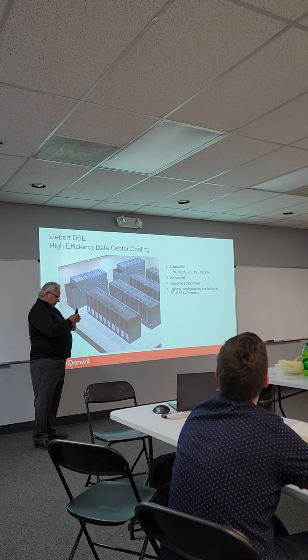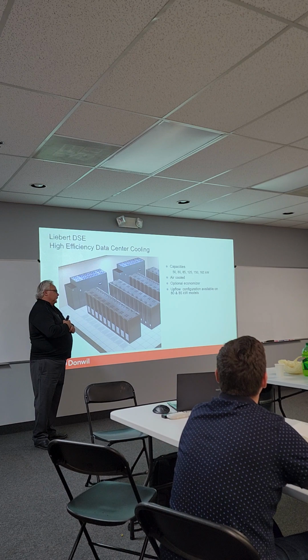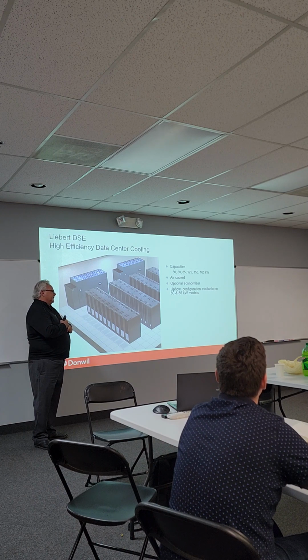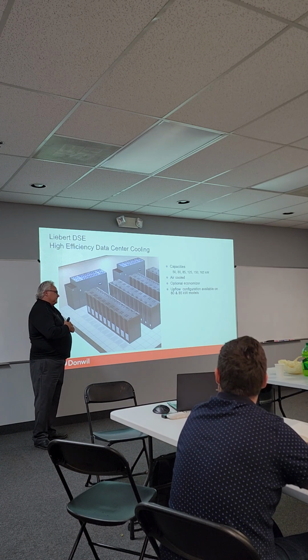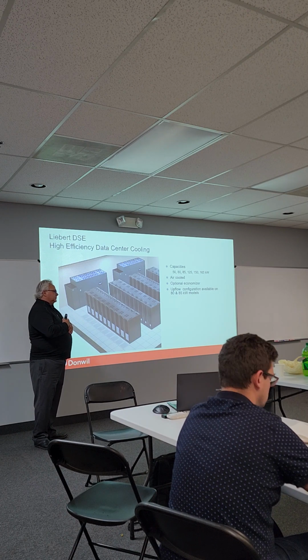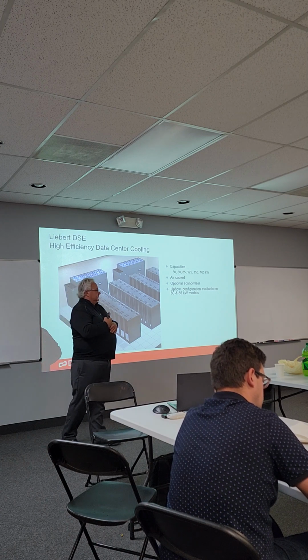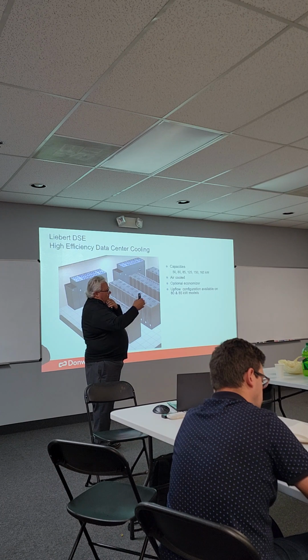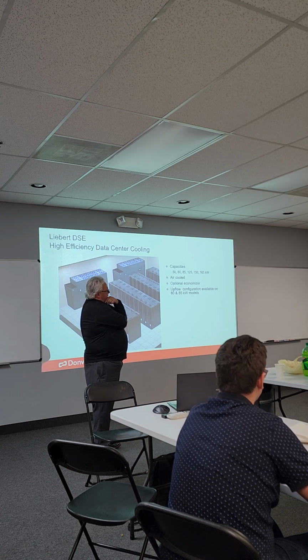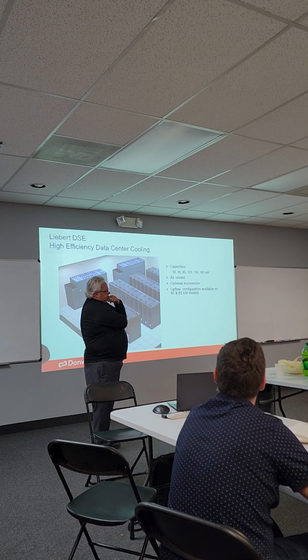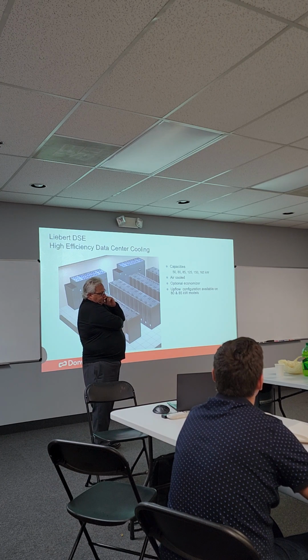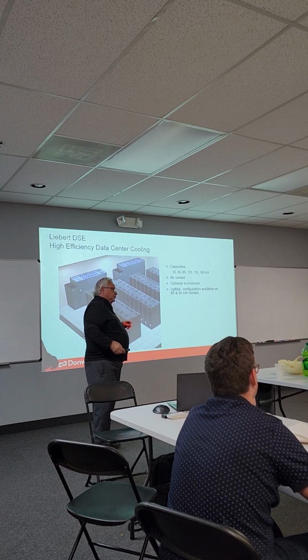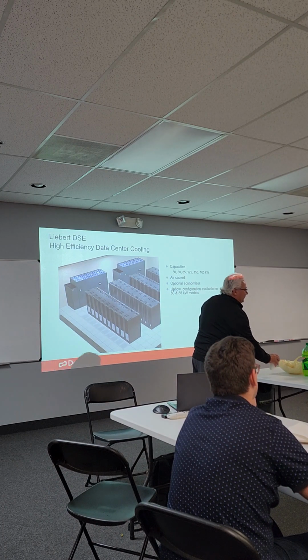Shuts off. Yes, sir. Are you saying that when you say sensible cooling only, the humidity doesn't enter into it? It does, but it's not as much as it used to be. The manufacturers of these computers and servers, their range is like 20 to 80% right now, sometimes even higher and lower than that. So you don't have to have 50% all the time? Not typically anymore, but in some cases some people are very particular about static electricity. That's why they want to keep the 50%. Anyone I ever had that did the cooling, brought the humidity down, they had to put a humidifier on there to put it back in. Yeah, that's what we did.